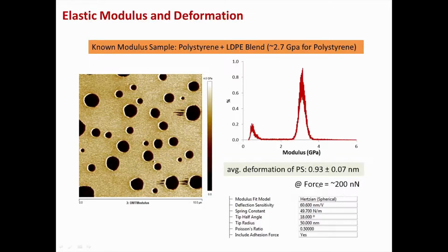Once we did that with a force of almost 200 nanonewton, and indenting it for about 1 nanometer or so, we get this 2.9 to 3 GPa measurement of the polystyrene sample. So we are kind of sure that if we get a deformation in this range, our modulus numbers will be like 2.7 GPa. So now if we go back and do the ACI samples measurement, we will have some surety that the measurements are right, or whether something is going wrong.